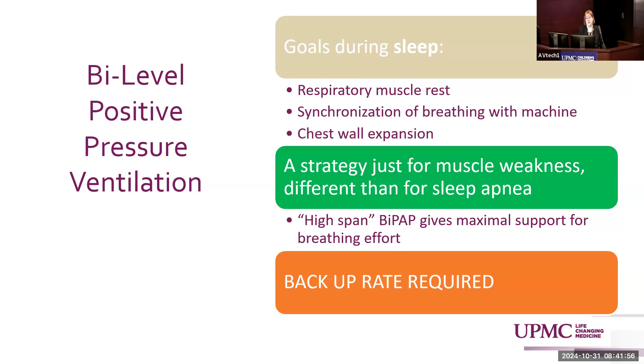strategies. So if I set like the CPAP at 6, we would then set the IPAP at 16 or higher. And you always want to make sure that you have a backup rate. And people are like, well, sometimes they're triggering it on their own. And that's true. When they're well, they can trigger it on their own. But when you get sick, you can get significantly weaker and you might not be able to generate those flows to trigger the machine. So you have to have that rate on for safety. It'll kick in if they get very weak.